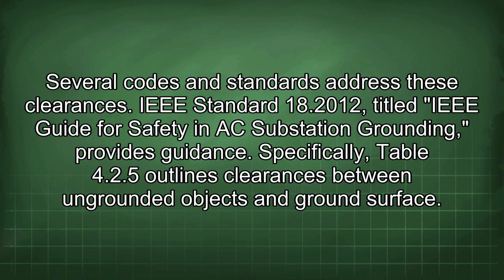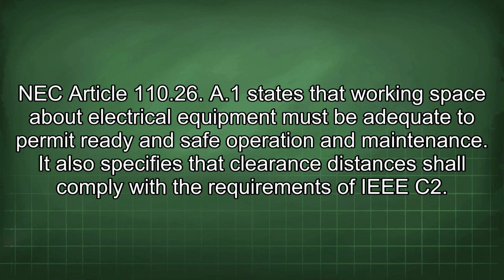IEEE Standard 18-2012, titled IEEE Guide for Safety in AC Substation Grounding, provides guidance. Specifically, Table 4.2.5 outlines clearances between ungrounded objects and ground surface. NEC Article 110.26(A)(1) states that working space about electrical equipment must be adequate to permit ready and safe operation and maintenance. It also specifies that clearance distances shall comply with the requirements of IEEE C2.